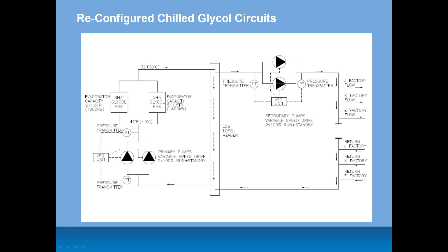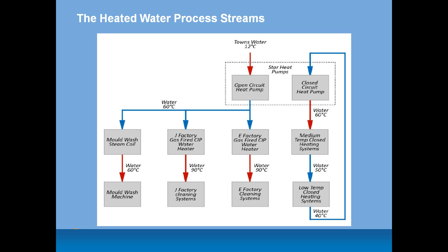Now, if you're sharp-eyed, you'll notice they're actually heating some of the water to 90, and we could have done that with a heat pump - we can now get up to about 90 degrees. But in this case, it made more sense to just do 12 to 60 with the heat pump and 60 to 90 using high-efficiency gas boilers.